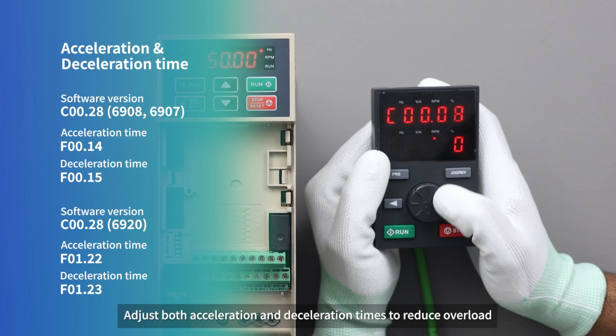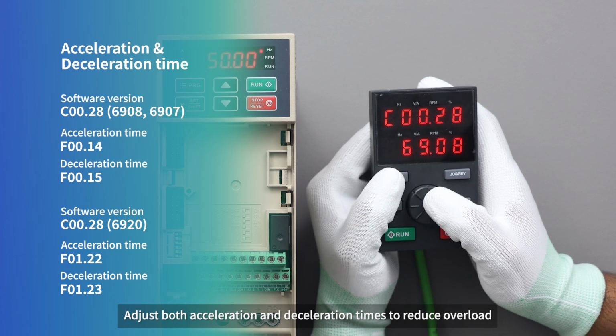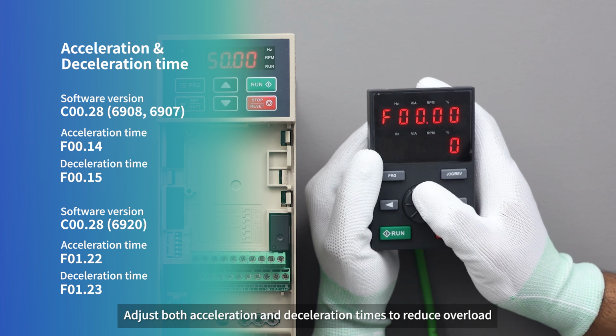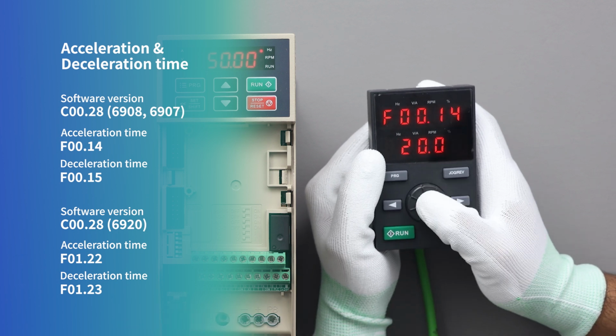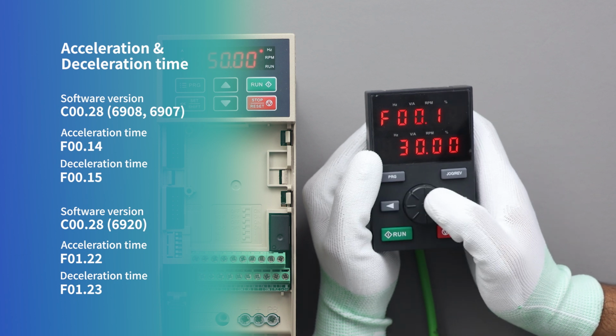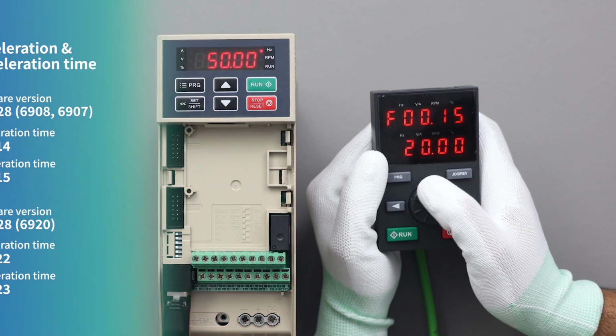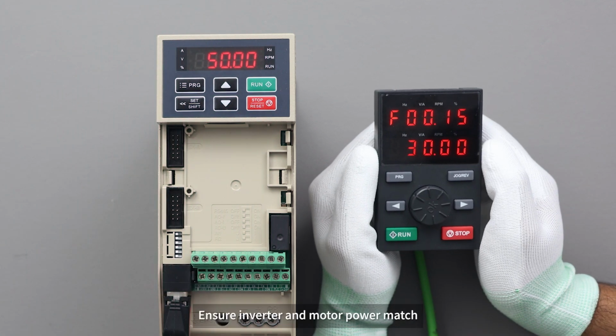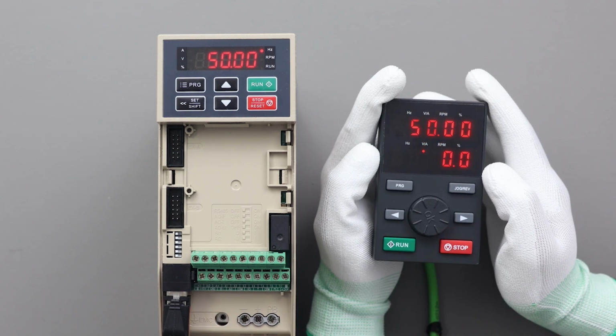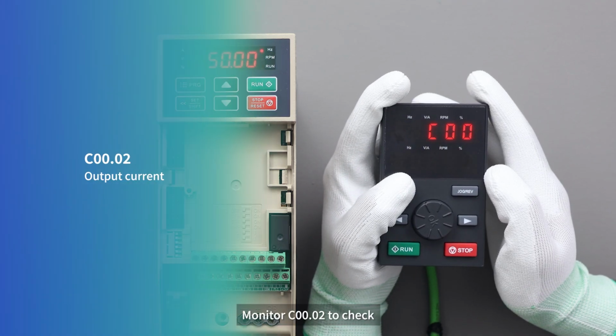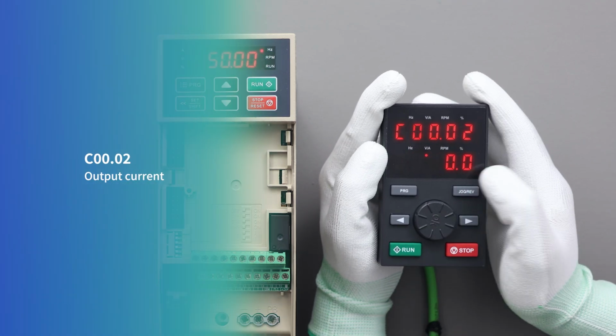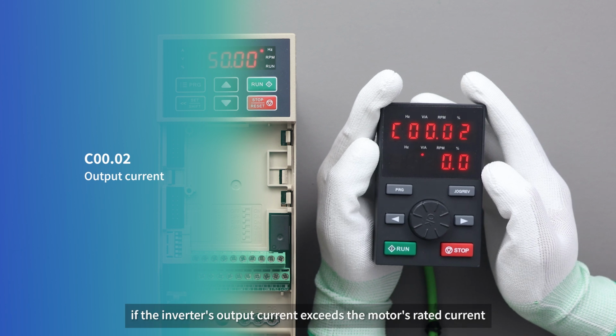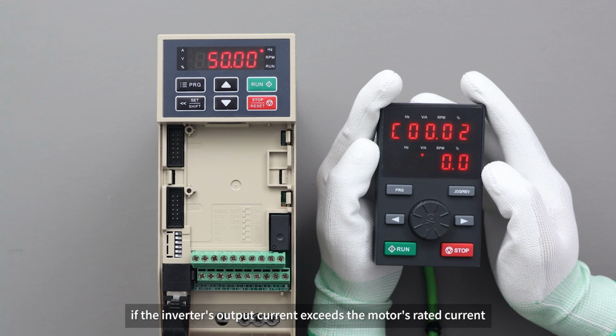Adjust both acceleration and deceleration times to reduce overload. Ensure inverter and motor power match. Monitor C00.02 to check if the inverter's output current exceeds the motor's rated current.